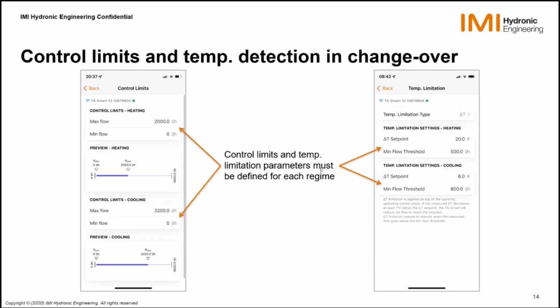For temperature limitation, here I've taken a screen capture for delta T. You get a delta T set point that by default is set for something more realistic for heating and something more realistic for cooling. And then the minimum flow threshold is the same idea, so it is 25% by default of the maximum flow currently set. So 2000 makes 500 liters per hour, 3200 makes 800 liters per hour. It just makes sense like that.